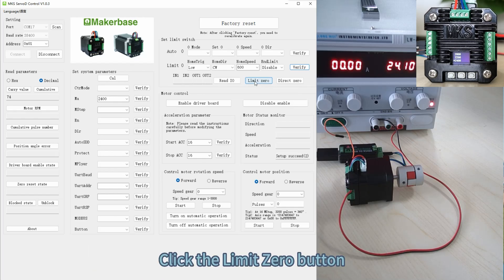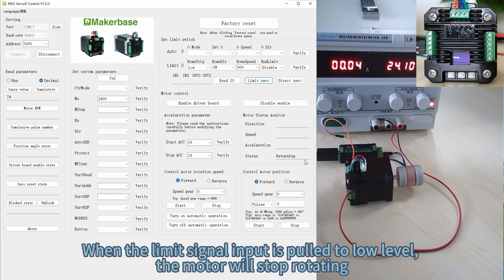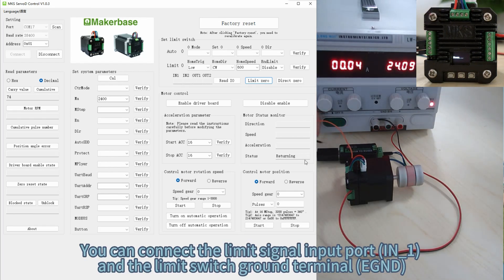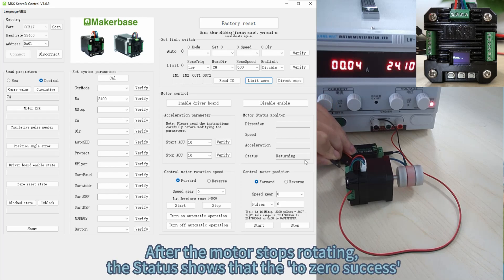Click the Limit 0 button. The motor starts to rotate and the status is displayed as returning. When the limit signal input is pulled to low level, the motor will stop rotating. You can connect the limit signal input port IN1 and a limit switch ground terminal eGND. After the motor stops rotating, the status shows 'to zero success'.